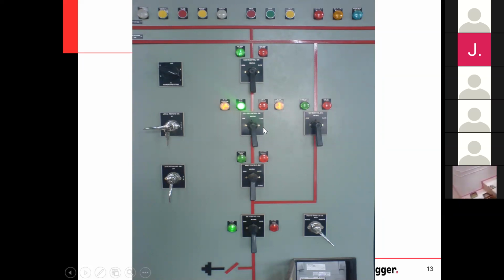See, we can close the breaker only if the system is synchronized. We all know this. Both sides of the breaker, that is on the top side as well as on the bottom of this breaker, should have the same voltage, frequency and phase angle. However, this condition is true only when both sides are live. There can be four possibilities here. Possibility number 1, both sides are dead. We call it dead bus, dead line.